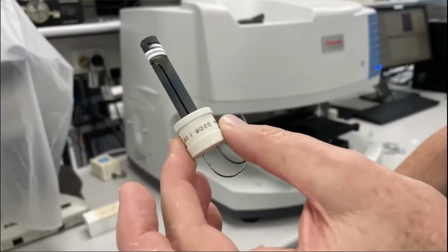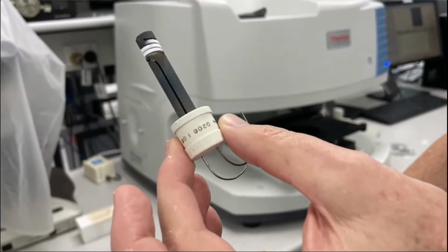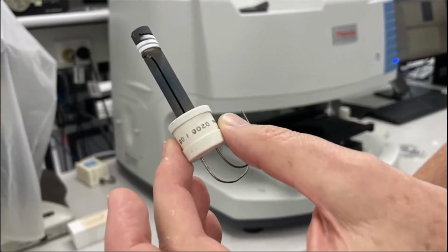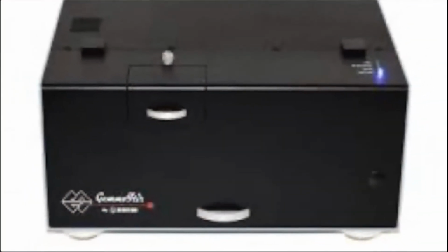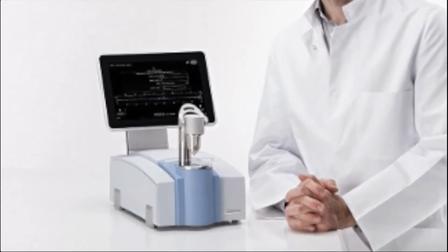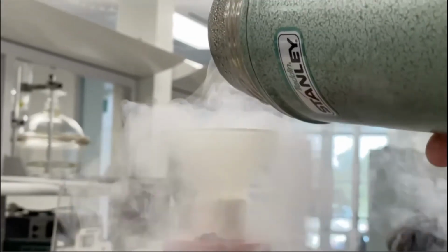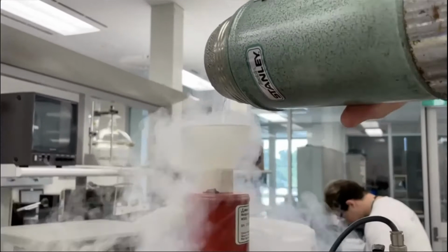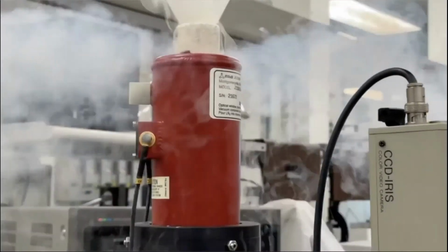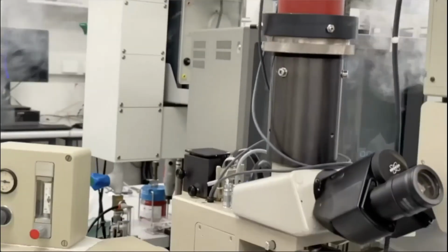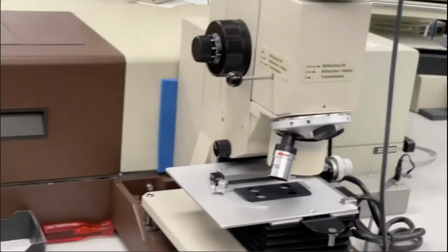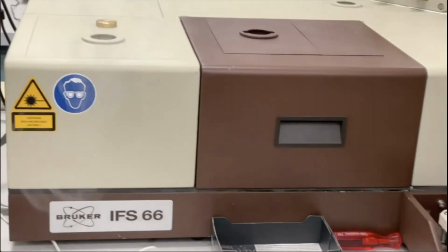The lamp source for mid-infrared spectroscopy is a glow bar. It glows much like a toaster element. Nowadays, the whole infrared system can be quite compact, a lot smaller than the model I have here at this university. The detector for this system likes to be cold, so liquid nitrogen is poured into a housing for the detector. What happens in the rest of the system? I'm not going to take it apart, but will try to describe how it works.